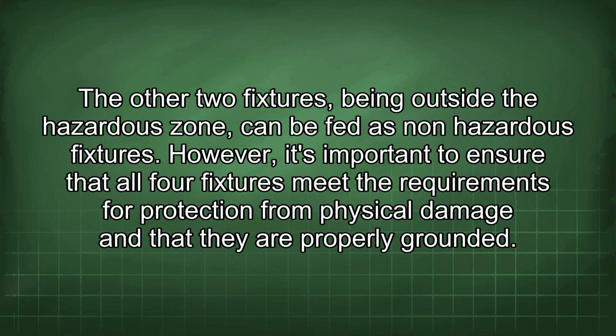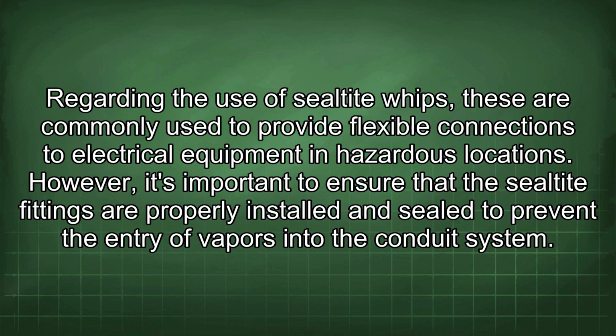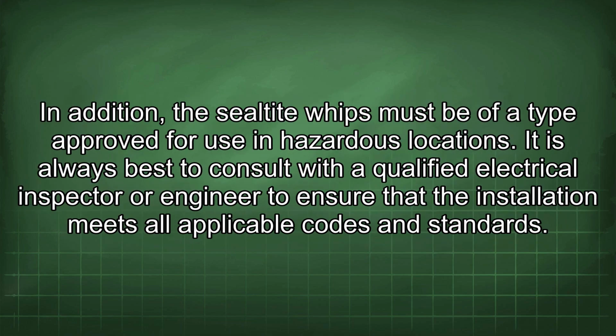Regarding the use of sealtite whips, these are commonly used to provide flexible connections to electrical equipment in hazardous locations. However, it's important to ensure that the sealtite fittings are properly installed and sealed to prevent the entry of vapors into the conduit system. In addition, the sealtite whips must be of a type approved for use in hazardous locations.